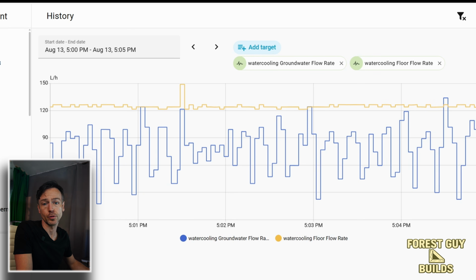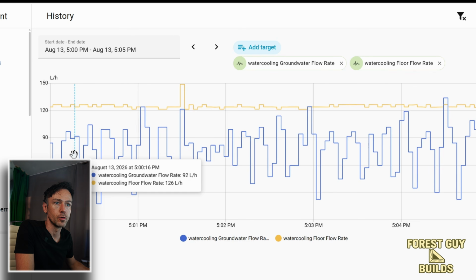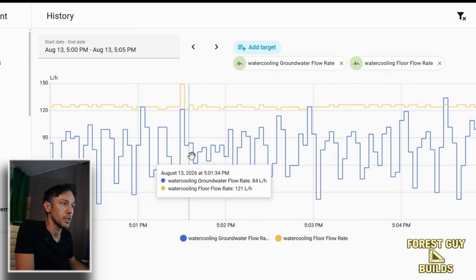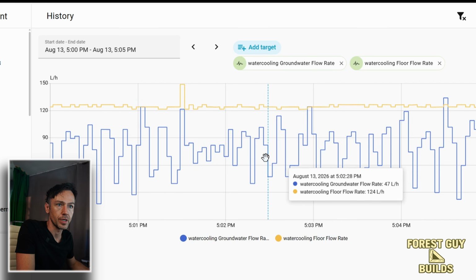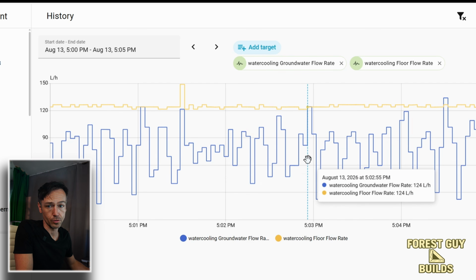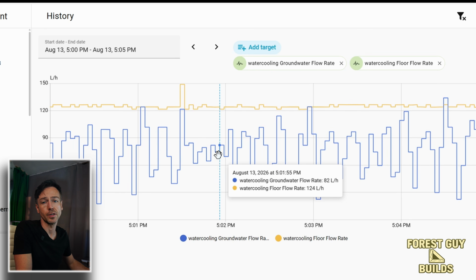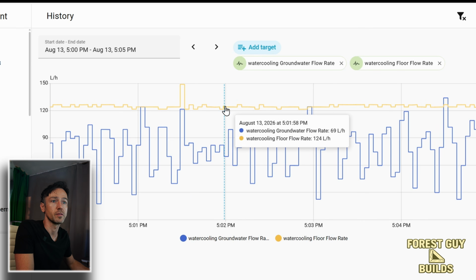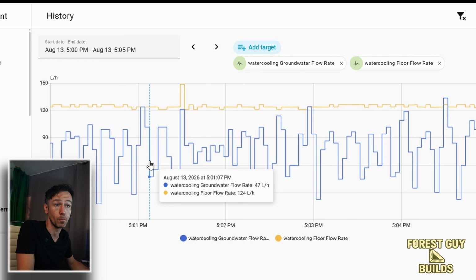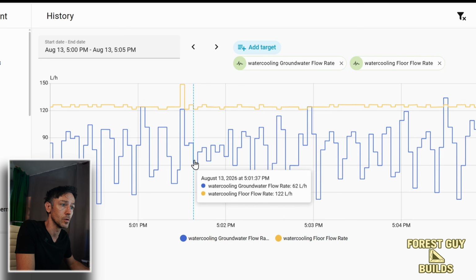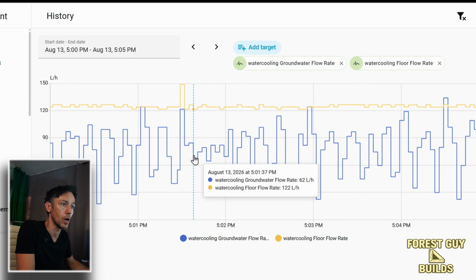Just as a check, let's choose a really small time frame and see what the measures are then. We still see that it goes quite all over the place, but at least we have a little bit better idea about what it is doing. I will also do some simple bucket measure tests and see how that compares with the results from the flow sensor. But at least based on this, we can quite safely say that on the floor circuit we have a flow of about 120 liters an hour, and on the cooling water supply side we have a flow of around 80 liters an hour.